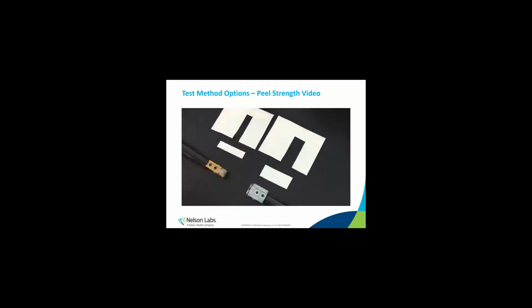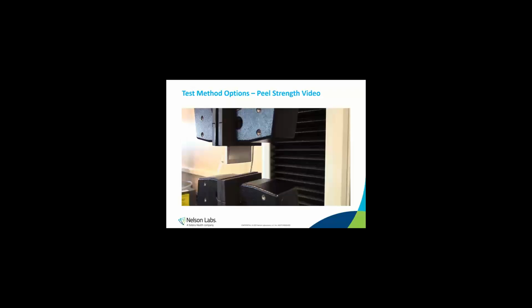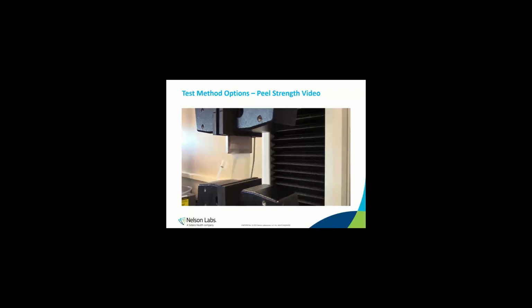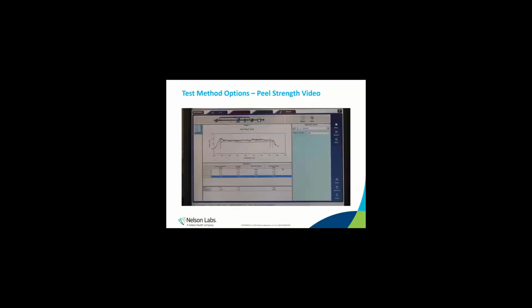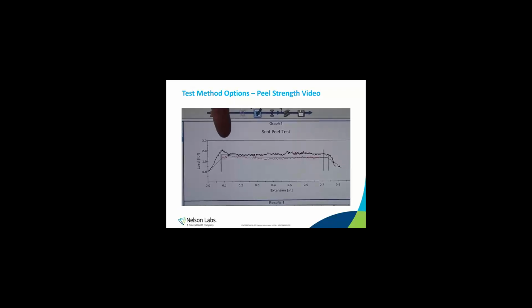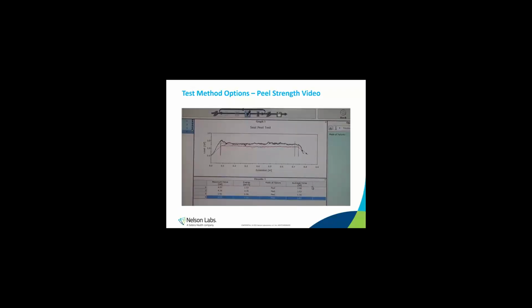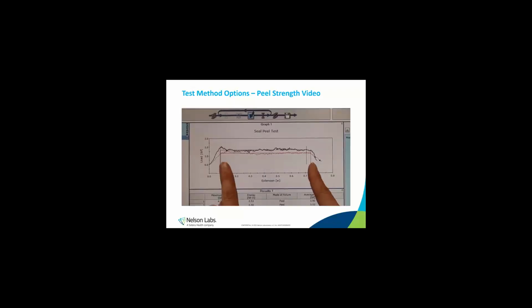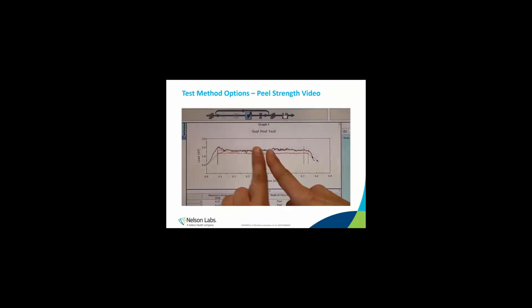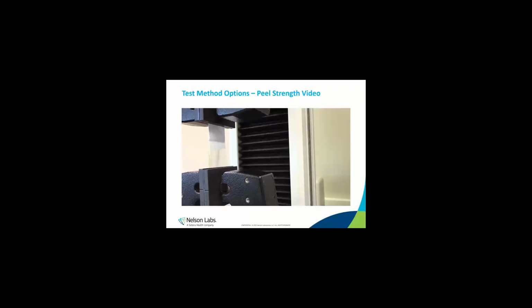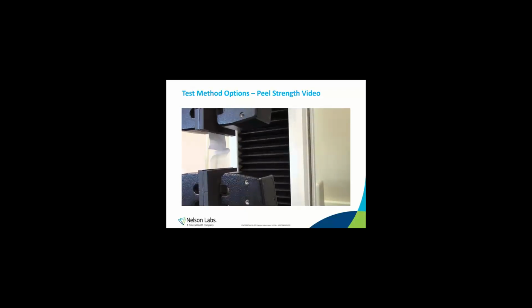So we would cut a portion of the seal, we pull it apart on the machine, and we measure the force required to separate it. Here's a graph. The maximum force would be the highest value on the curve. The energy is the area under the curve, and the average force is the average force from the middle. This is a typical peel.